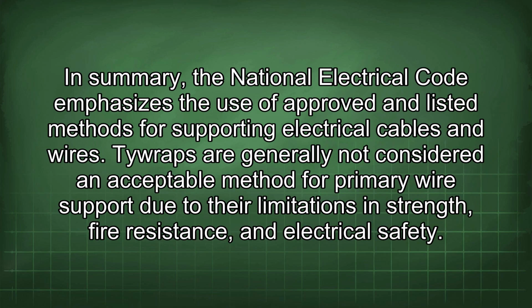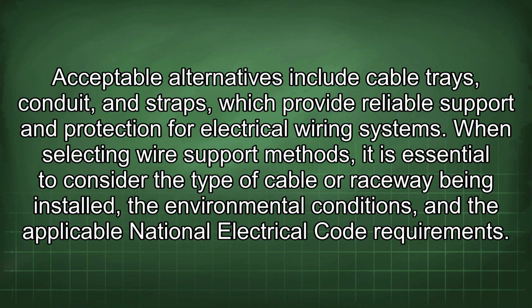In summary, the National Electrical Code emphasizes the use of approved and listed methods for supporting electrical cables and wires. Tywraps are generally not considered an acceptable method for primary wire support due to their limitations in strength, fire resistance, and electrical safety. Acceptable alternatives include cable trays, conduit, and straps, which provide reliable support and protection for electrical wiring systems. When selecting wire support methods, it is essential to consider the type of cable or raceway being installed, the environmental conditions, and the applicable National Electrical Code requirements.